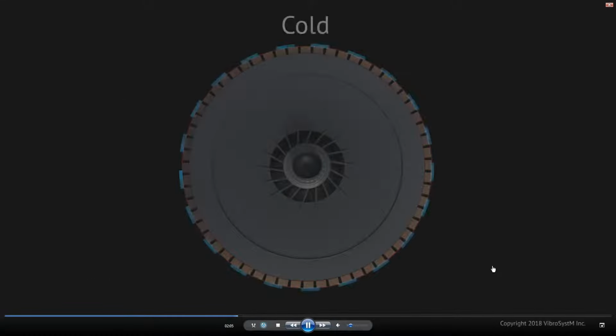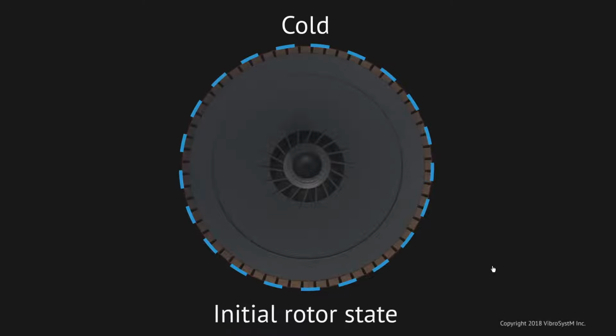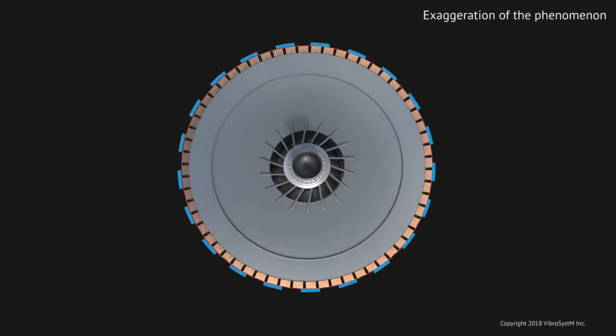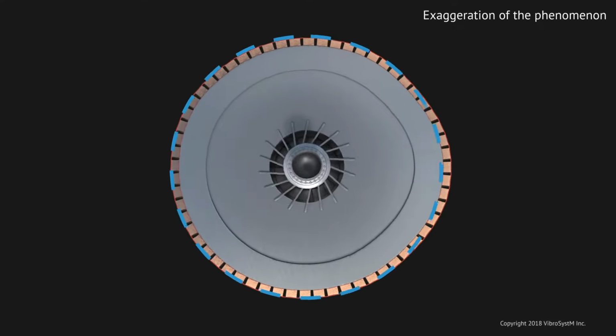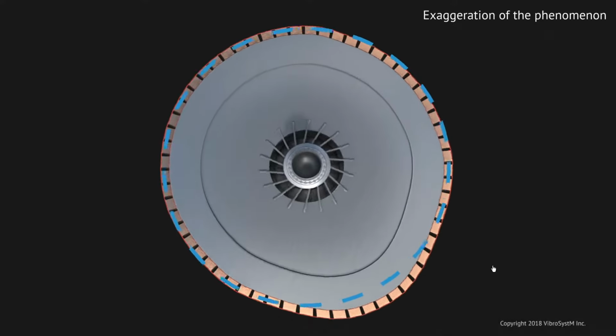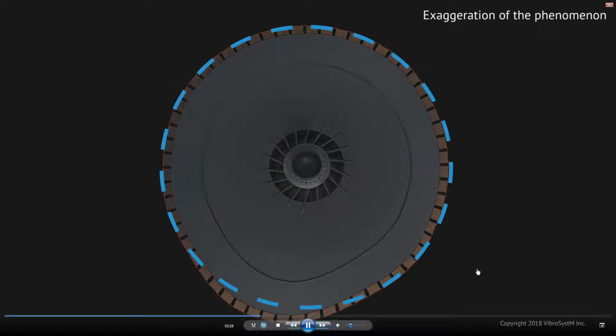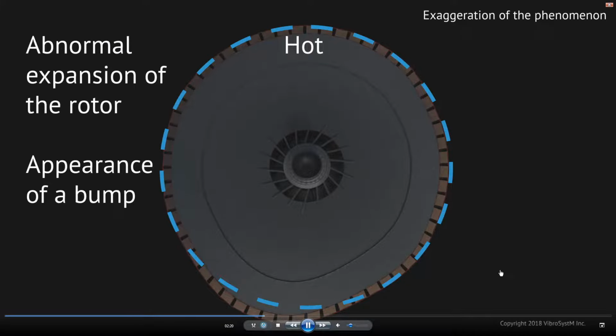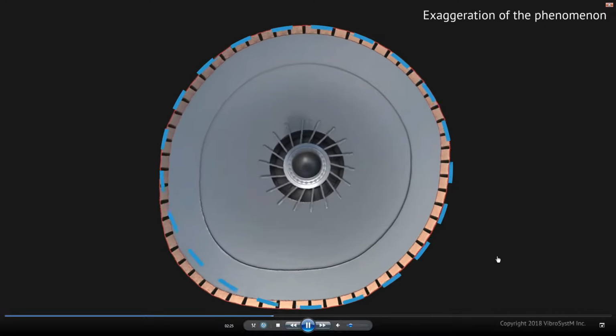Okay, so if we look at the rotor shape, if the unit is cold, let's say it's perfectly round, and as you increase the speed or as you increase the load, you will see rim distortions. And rim distortions are usually represented by not one pole sticking out, but you can see an entire section is actually coming off. Maybe not coming off, but is moving outwards at a greater rate than anywhere else. Okay, that's the type of analysis that you can perform with the air gap sensor. And it's quite common, by the way. I don't want to frighten anybody, but it's quite common.